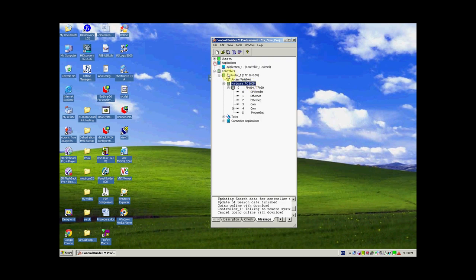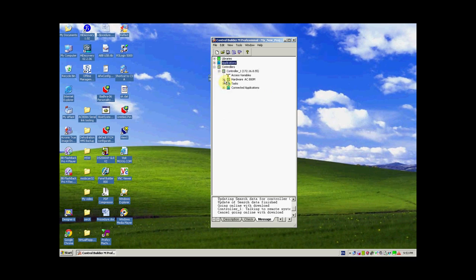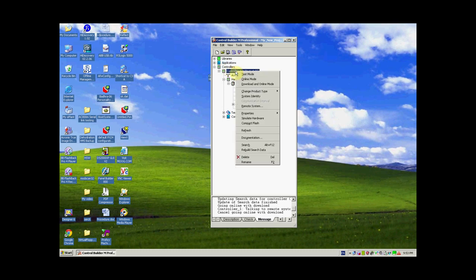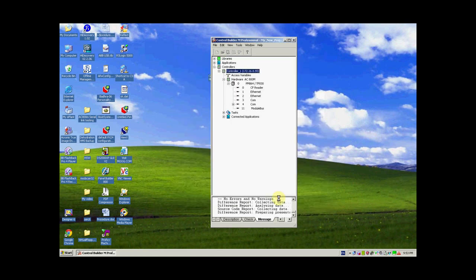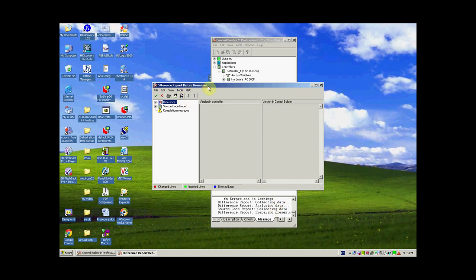We are now ready to download our first project to the AC800M controller. Although we have no program written, we can download an empty program. Right click on the controller and click Download and Online Mode. It will report a version mismatch. Since the controller is being downloaded for the first time, click Continue. It will then provide a difference report, which compares the software version already in the controller against what we are about to download.